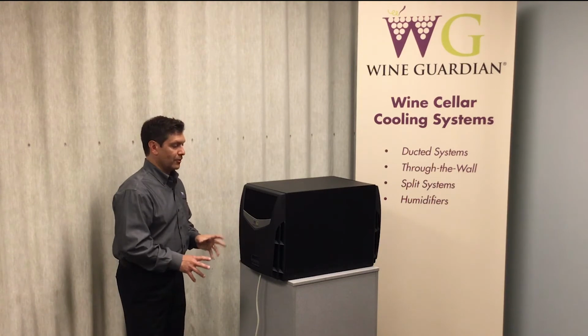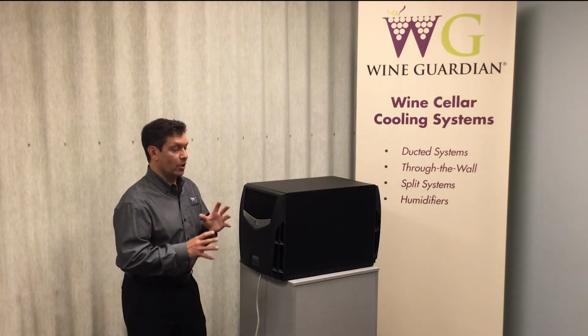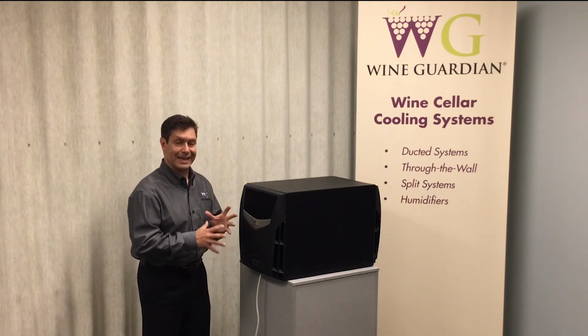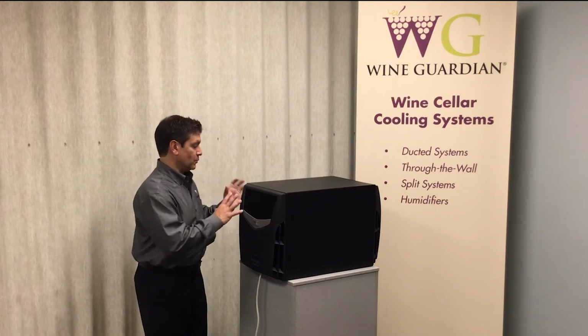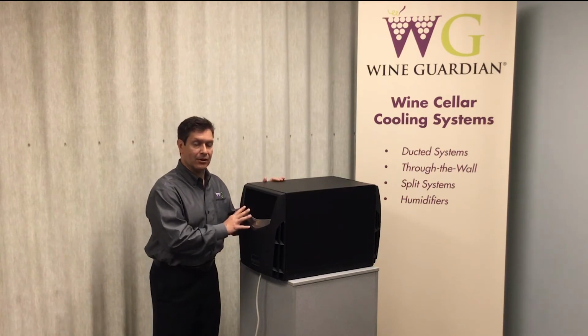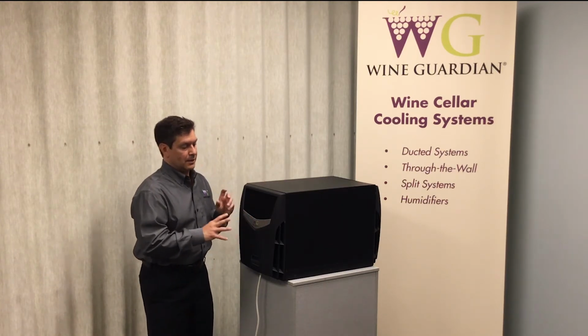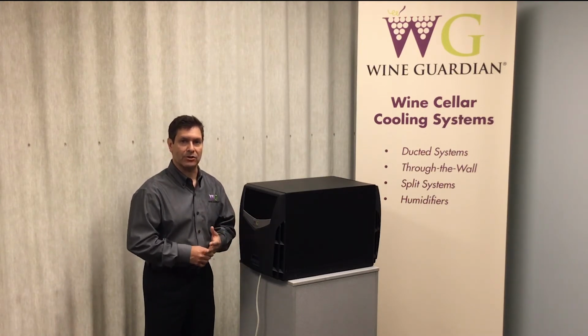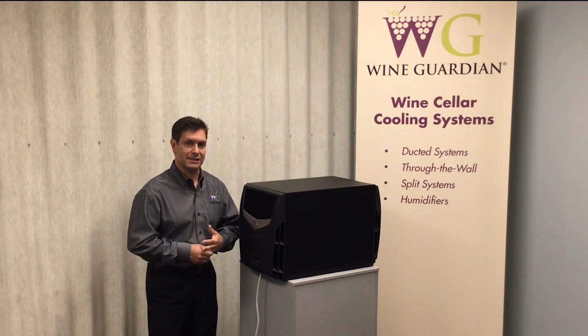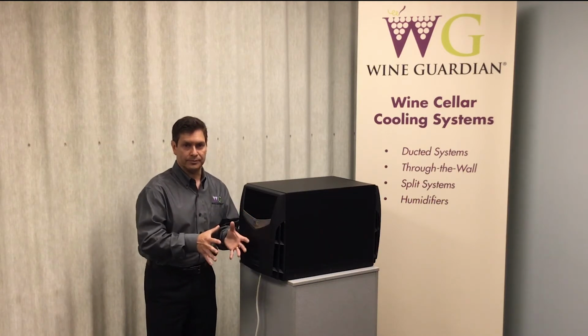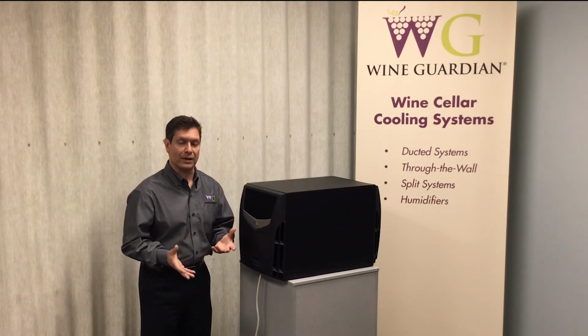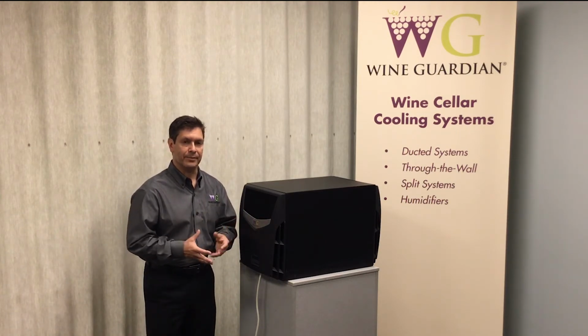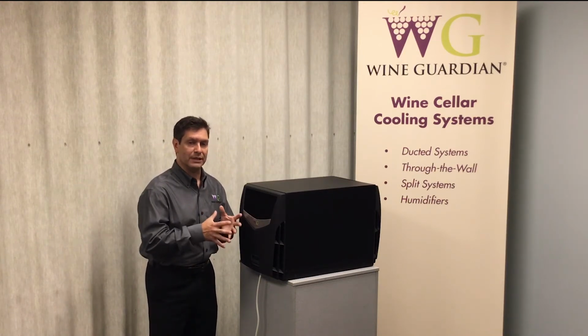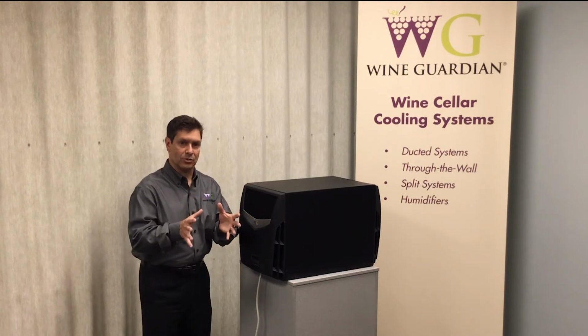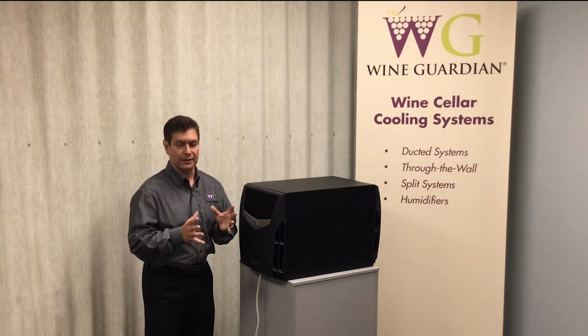As far as some of the options that are available on the system, we're the only wine cellar cooling unit that offers a through-the-wall with a heater option, and it's ETL labeled. One thing that we didn't mention, one of the features, is that this unit has an ETL rating, so it's agency approved. With that is a heater option. It's a 500 watt heater option, and similar to all of our ducted units, that heater acts to warm up the wine room. Say you've got a wine room that has 3 outside walls in an area that's extremely cold in the wintertime. That heater will make sure that it doesn't get too cold in the wine space. It actually heats the air up back into the wine room. So it's either heating or cooling, but not both.